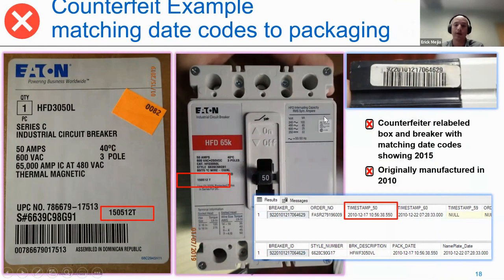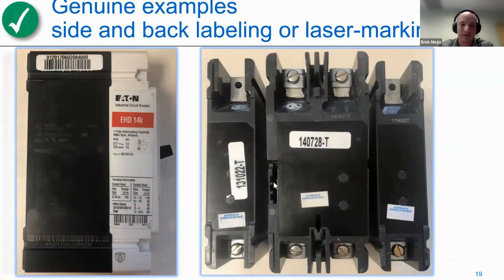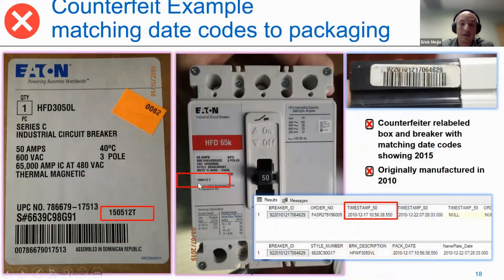If those three don't match, that's a huge red flag, and you automatically know that breaker is counterfeit. For example, this breaker was actually manufactured 2010-12-17. This right here is the year it was manufactured, it says 2015 - this would be the month, sorry about that - the two following digits would be the month, and the last two digits the date. Clearly it does not match when it was actually manufactured. That's another key thing to look at when comparing a counterfeit to an authentic breaker.